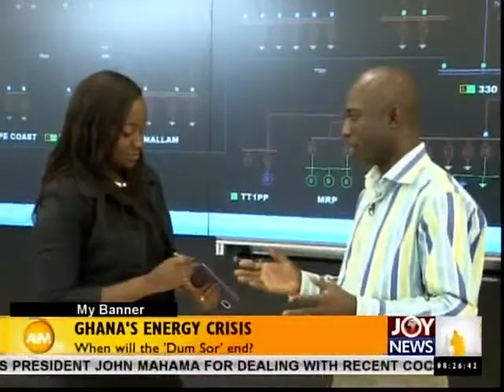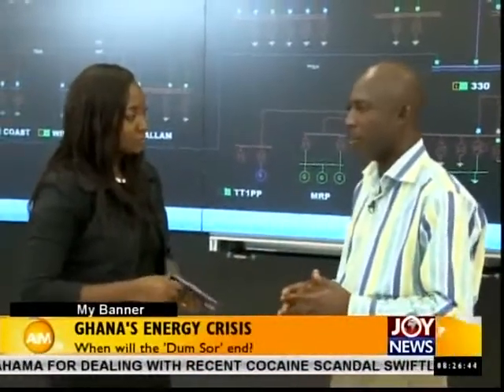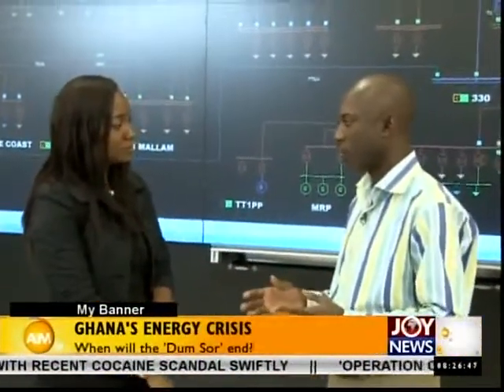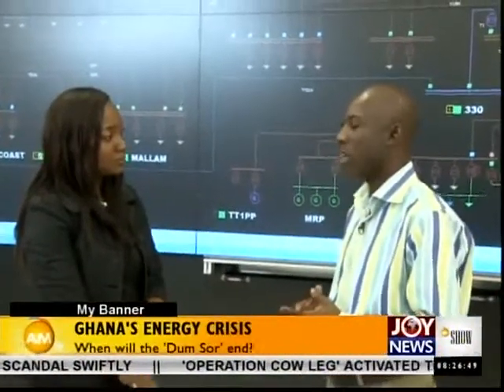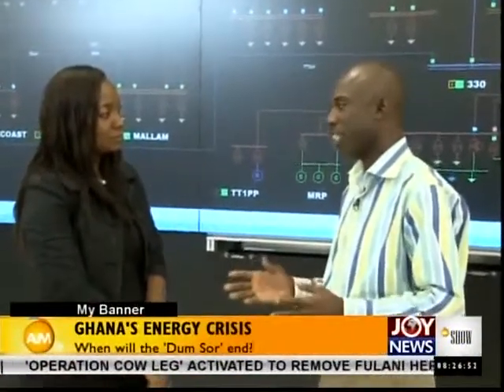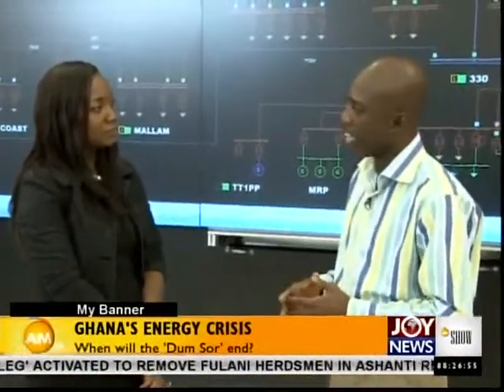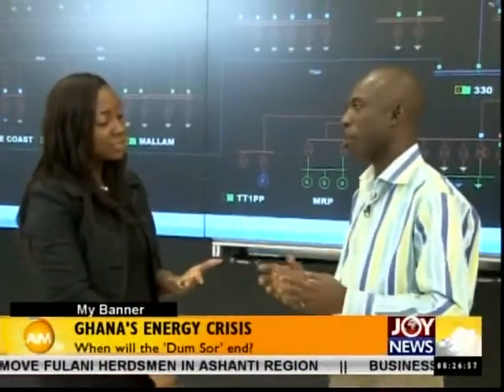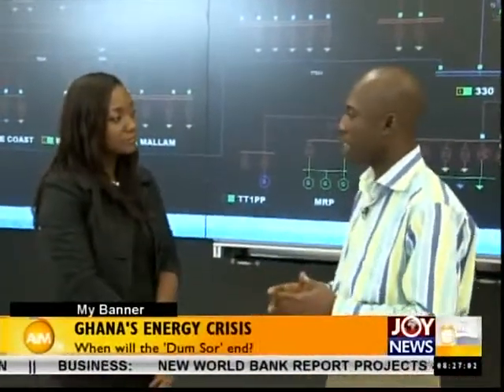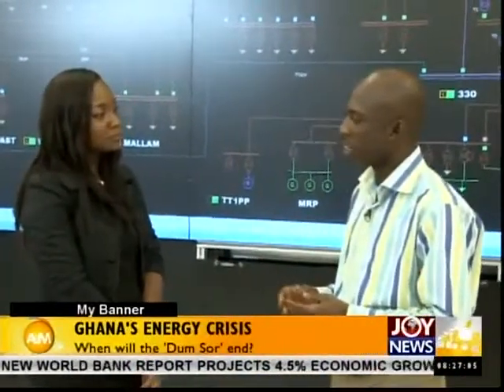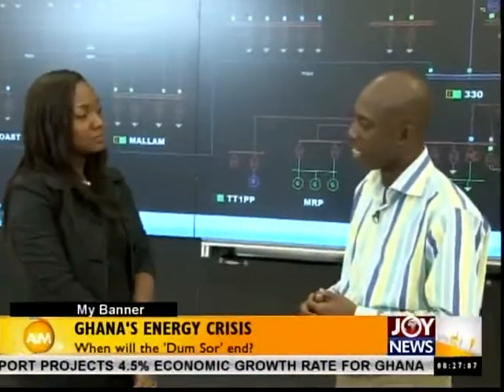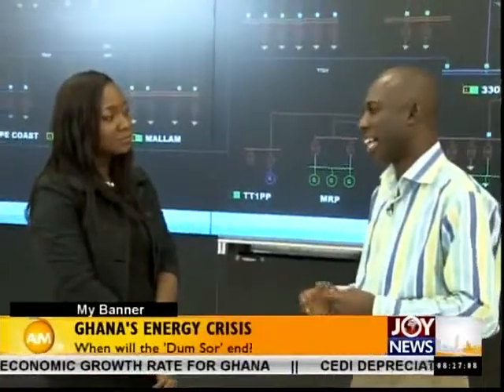There are many different reasons why you could go off. If you take first the load shedding we've been on, it is precipitated by a shortage in supply. If you put together all the generating capacity we have as a nation right now, it is not up to the amount of demand we have on the grid, and that requires that some amount of demand must be cut off in order to balance demand and supply.